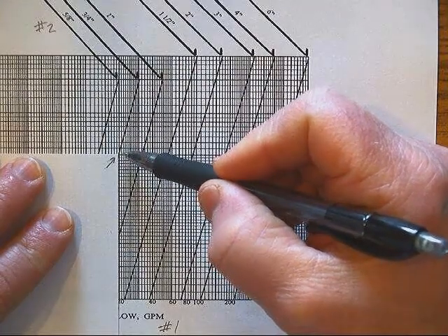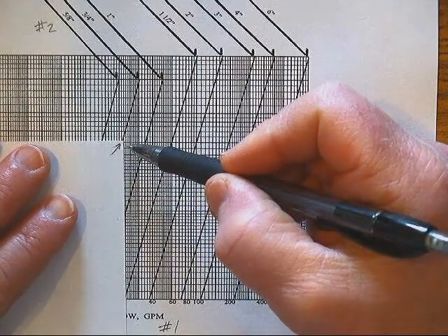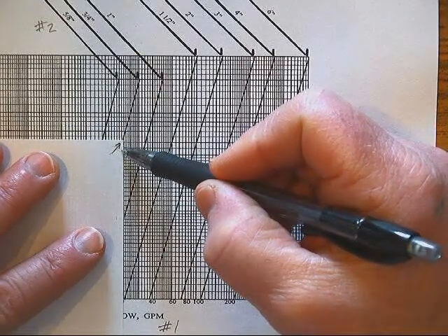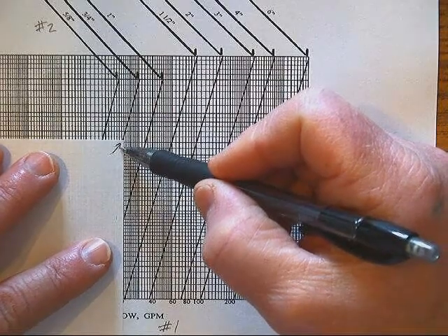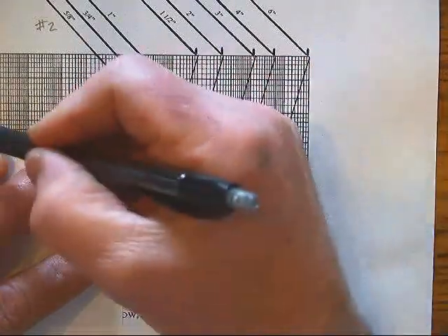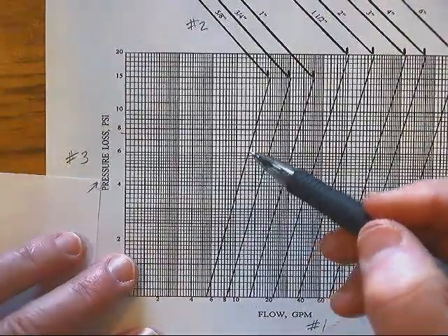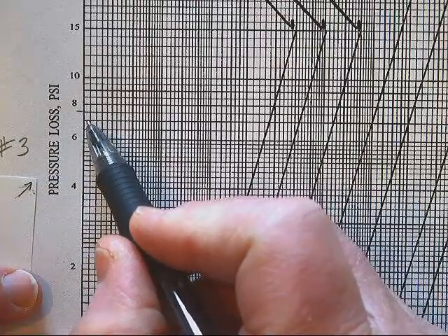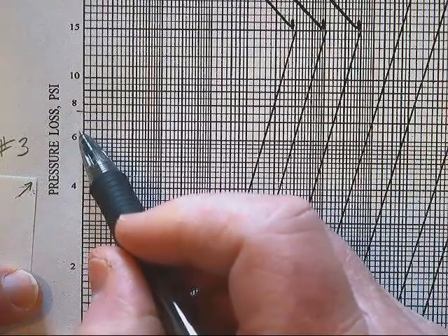Now we were at 22.2 GPM, so I'm going to go 21, 22 GPMs, and make sure I'm all square here with my lines. Alright, and we're going to intersect right about there. We said it was about 22.2. I'm going to make a tick mark right here at the closest line. As I look at that, it appears that we've got 6, we'll call this 7, this middle line here. We'll call it 7.5 psi loss through a 3/4 inch meter.